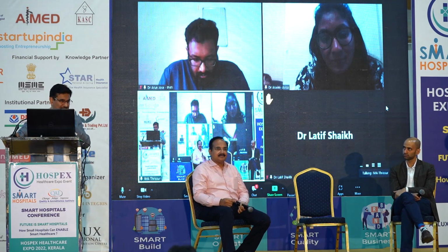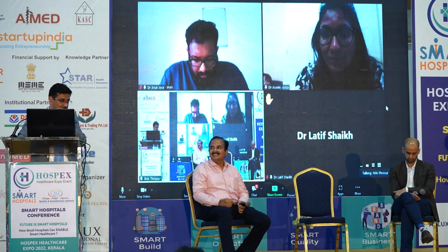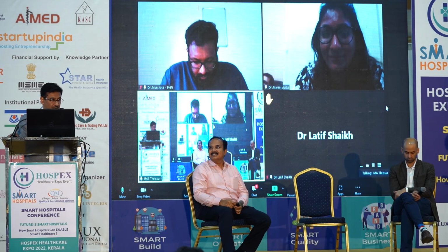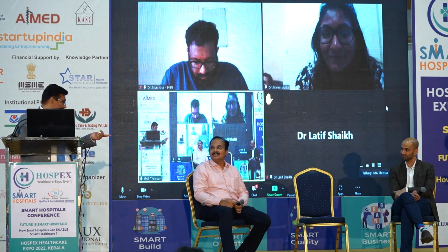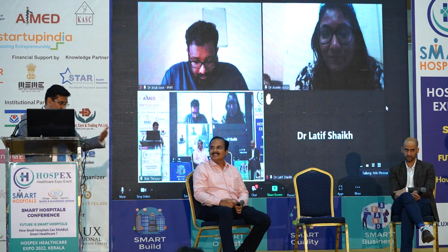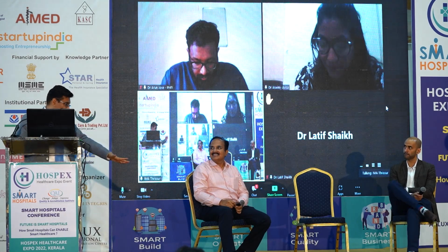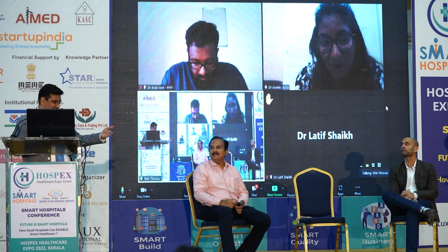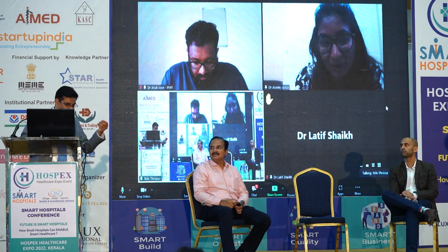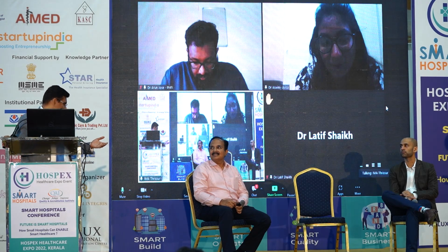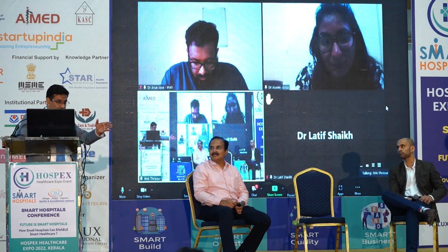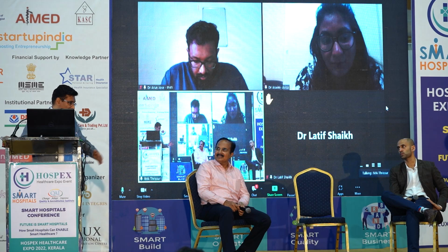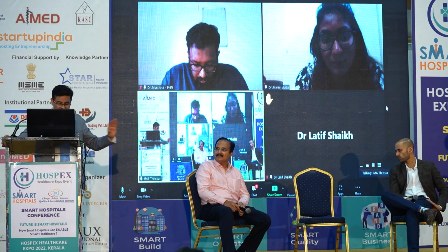Yes, I think that's a long discussion we can get into, which I don't want at the moment, because to be very honest, you have raised a very good point. I have seen a primary health center where a patient with a glucometer was coming in and the person was taking a reading, and I looked at it and said, I can guarantee that this is not working correctly. Why? Because the battery is weak. You have not even checked the battery life and how it is working. If your battery is weak, it's not going to get you the results correctly, and you are missing so many patients in the line. So I would suggest that you use the same quality assurance procedures for your devices as you would in a hospital. That will make your system perfect and pakka.